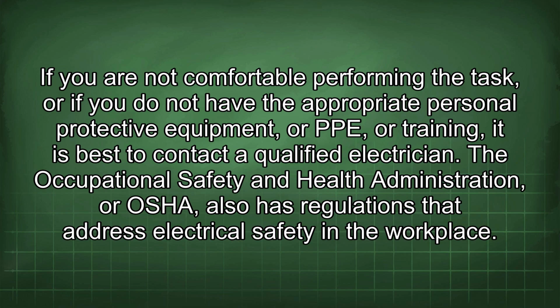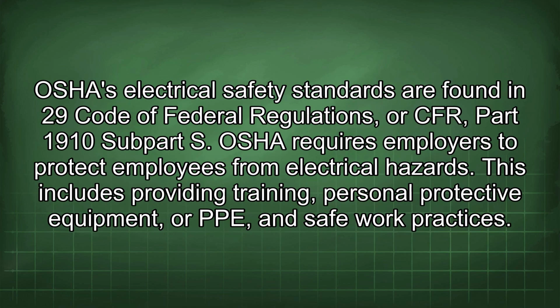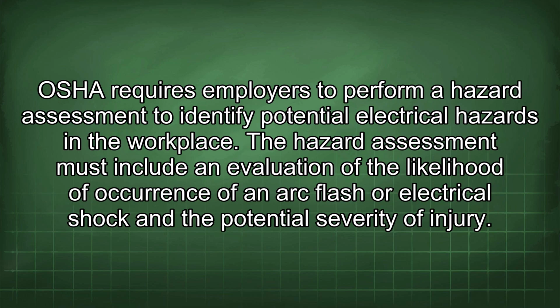The Occupational Safety and Health Administration, or OSHA, also has regulations that address electrical safety in the workplace. OSHA's electrical safety standards are found in 29 Code of Federal Regulations, or CFR, Part 1910 Subpart S. OSHA requires employers to protect employees from electrical hazards. This includes providing training, personal protective equipment, or PPE, and safe work practices. OSHA requires employers to perform a hazard assessment to identify potential electrical hazards in the workplace. The hazard assessment must include an evaluation of the likelihood of occurrence of an arc flash or electrical shock and the potential severity of injury.